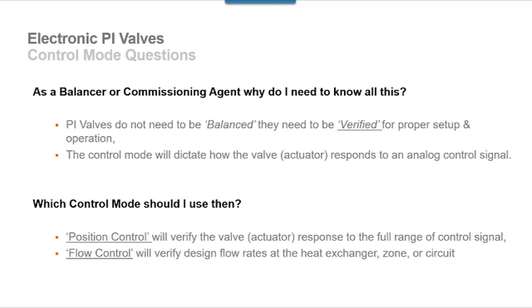This kind of goes back to control mode. If the control contractor just wants to verify that his control signal is tracking, putting the valves in non-pressure independent mode allows that. You watch the actuator and it will go the full span. If I go to flow control, now it's going to be controlling based on flow, which may or may not exhibit full span. I know in the beginning we got a lot of questions about, hey, your valves aren't working. They're not opening up fully, depending on where they're set. You're absolutely right. They may not be opening up fully, but they're working fine.